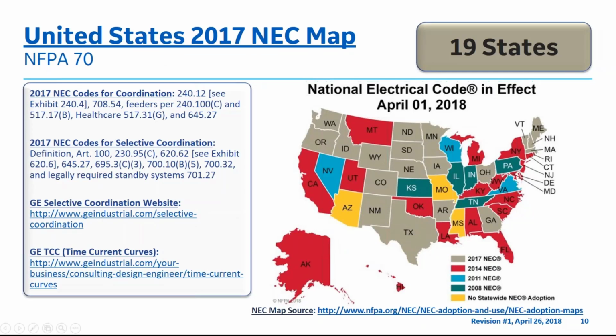On the left, there are references to at least 6 code references for coordination, which typically refers to the 0.1 second and above region in a time current curve. Please check with your local AHJ about what time interval is required to meet this code requirement, as the NEC doesn't specify the time interval. In addition, there are references to at least 8 code references for selective coordination, which typically refers to the 0.01 second selective coordination in the instantaneous region of a time current curve.